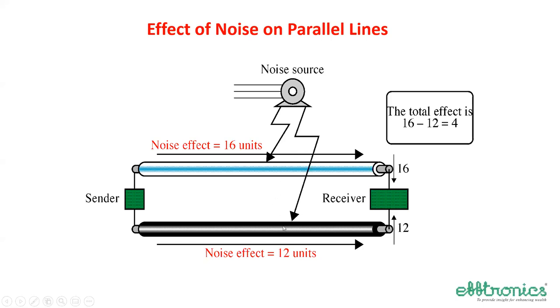And it is just a little farther away, maybe 3-4 units less noise is received here. So when a sender, a transmission is here and a receiver is here, ultimately, a noise of 4 units is combined or added to the signal at the receiver. And these 4 units will be much more than the minimum available, because we are talking about 2 milliampere, 5 milliampere signals. So it is just not acceptable.